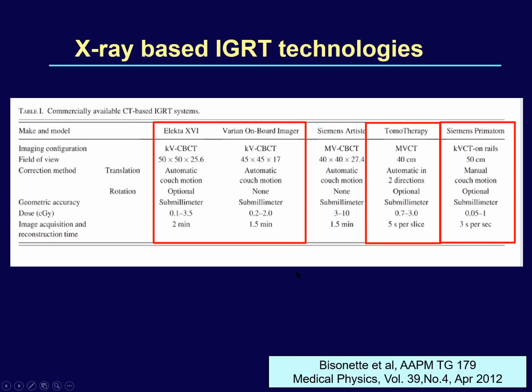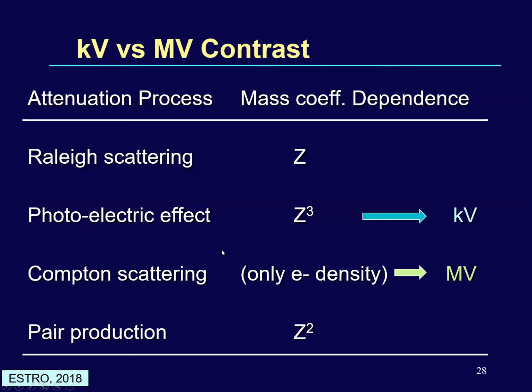However, the MVCBCT for the Siemens was reported to give a larger dose of 3 to 10 centigray, but in tomotherapy, since they use a degraded MV source for imaging, the doses were in the order of 0.7 to 3 centigray. The other, KV imaging, offers much less dose.